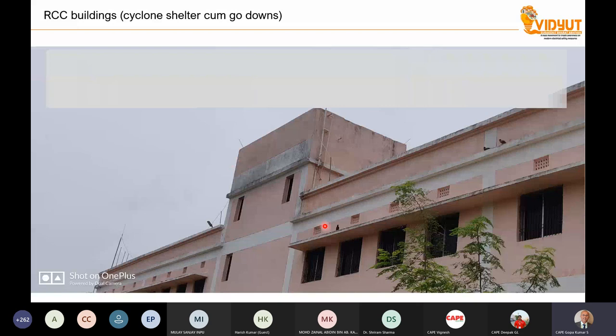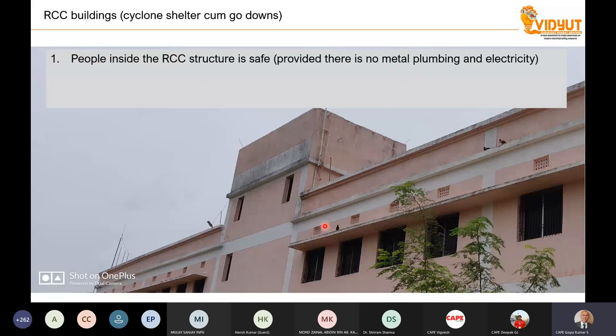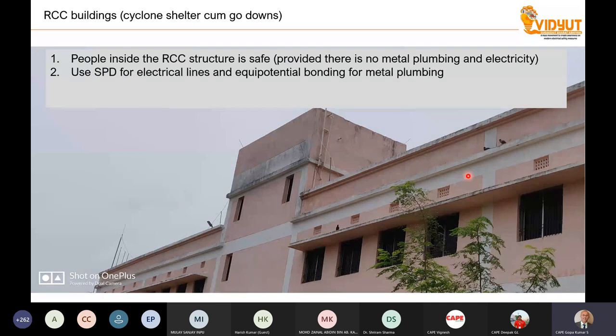Now, for cyclone shelters, this kind of RCC building, the people inside the building are protected, provided there is no metal plumbing and electricity inside the building. If there is metal plumbing and electricity inside the building, you have to make an equipotential bonding. Otherwise, people inside are protected. Now, whatever rod and down conductor you are going to give for these kinds of buildings is to protect the structure. Otherwise, lightning will strike the structure and the concrete, or a piece of concrete, may break.